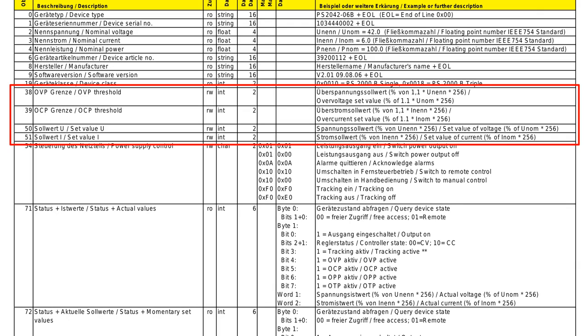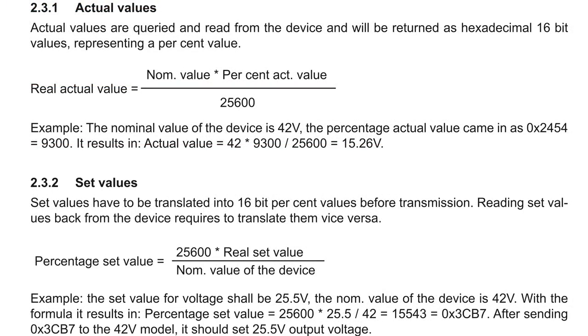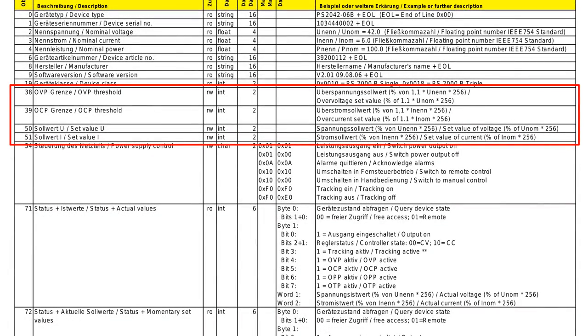This is not actually times 1.1 - times 1.1 of this is the maximum. How you send the data, you should refer to the programming manual, and it's pretty hard to understand what they mean here. There are some examples of the actual value and the set value. The nominal value percent, the actual value divided by this - you should implement it as defined here, actual value and set value. Again, you don't send the value, the percentage of 1.1. The maximum is 1.1, so you can go up to 46.2 volts.